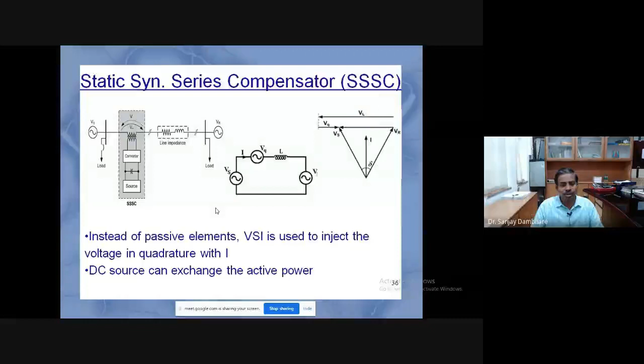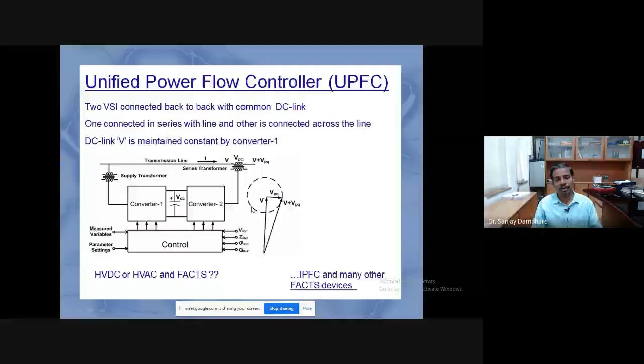As I said, the hybrid power flow controller, which is UPFC. So this hybrid power flow controller is the combination of both, and you can put the control voltage in series with the transmission line, which has some phase angle and some magnitude, and that control voltage can control the active power as well as the reactive power, because this V of PQ control voltage, which you are putting in series with the transmission line, can have the active as well as reactive component.